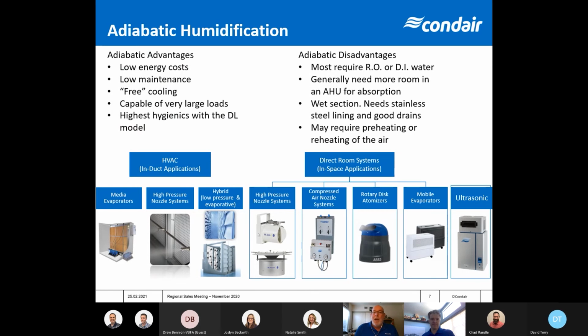But the really great thing about these is they're very inexpensive to run. We're not boiling water. So these are very economical to run, especially when we have large loads. This is usually a really great way to go. And I'm going to run through a few of these products down at the bottom. At the bottom left, we have what we call our ME units, or evaporative media. So we're just running water through the media, drawing the air across to cool and humidify the air. This has a very low cost of operation. We can use any kind of water on here we want, either potable, RO or DI water.